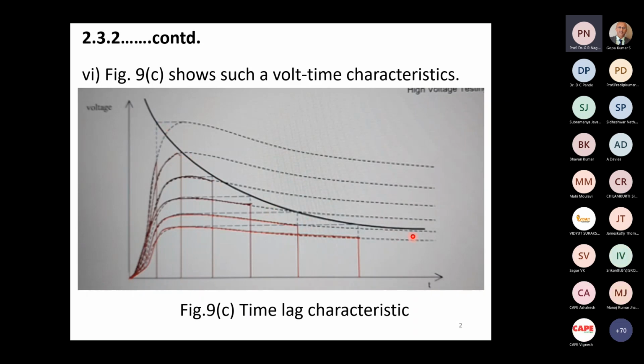So it's highly probabilistic. The important point for us to note is that typically the 50% breakdown voltage occurs approximately in the time range of 10 to 15 microseconds, with a variability of 5 microseconds. That's the time range in which the typical 50% breakdown voltage occurs.